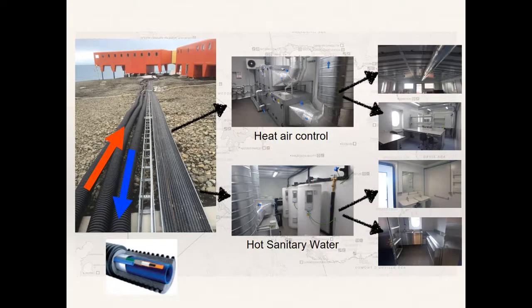The hot water that reaches the modules is used in 2 ways. The first, through water-air exchangers to heat the air that is used to maintain the temperature inside the buildings at a comfortable 18 degrees Celsius. And the second, to store sanitary hot water that can be used in bathrooms and kitchens.